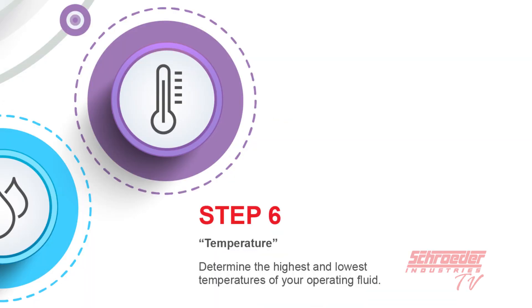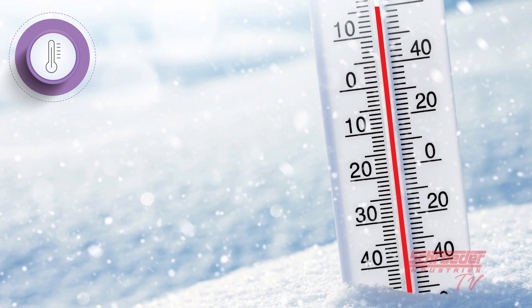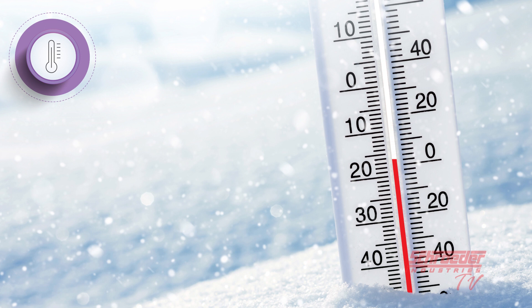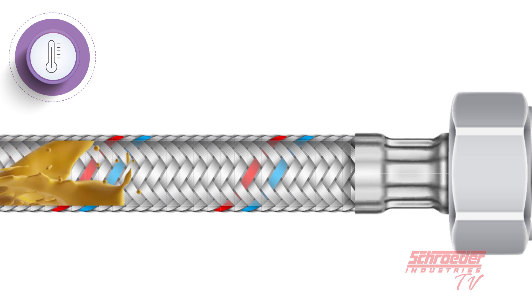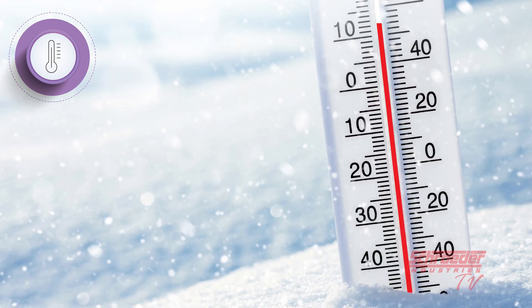Step six is to determine your maximum operating temperature. Temperature will help you verify the use of the proper housing size and, more importantly, viscosity. Viscosity will affect the differential pressure and will need close attention. Knowing your cold start temperature is also very important.